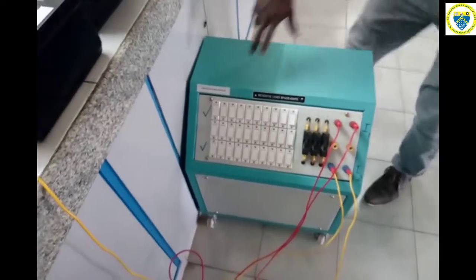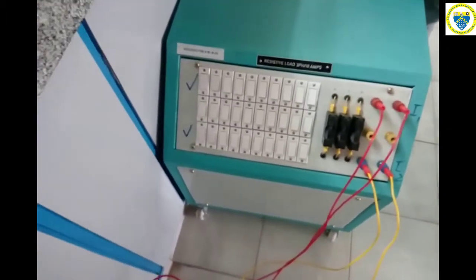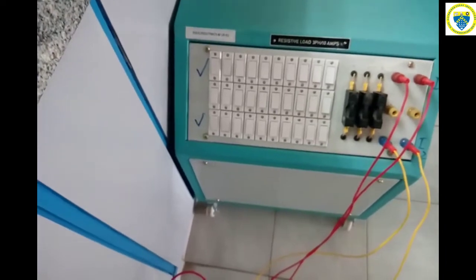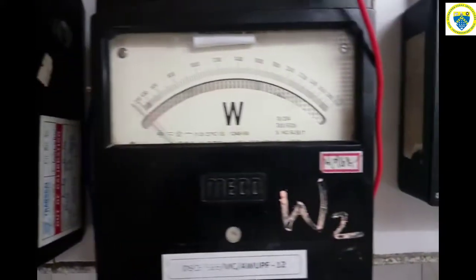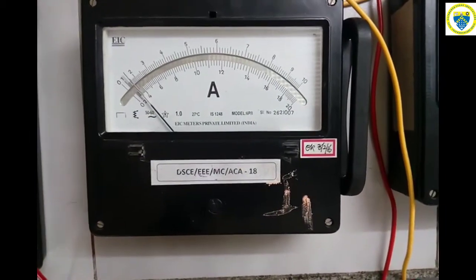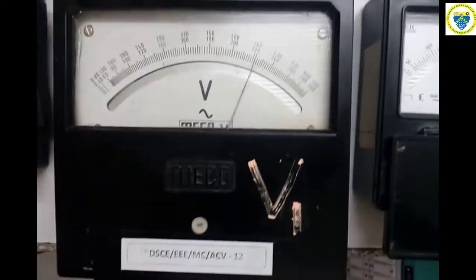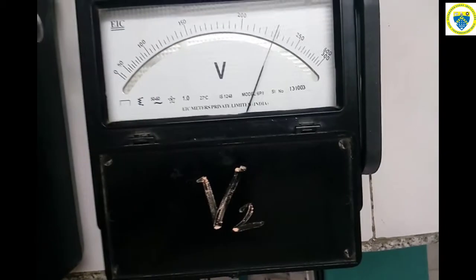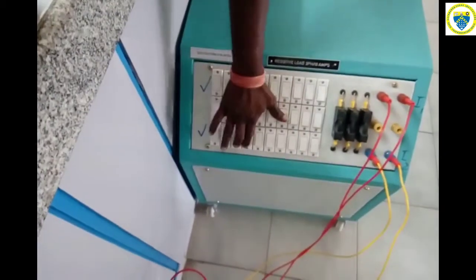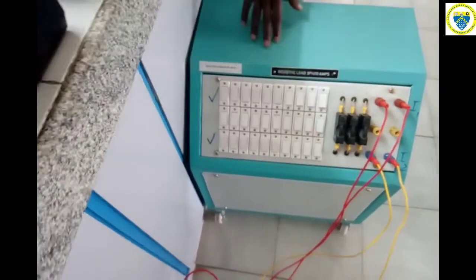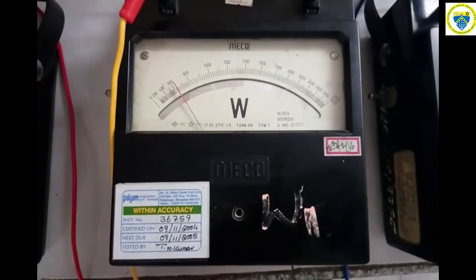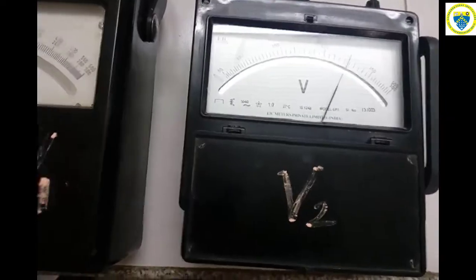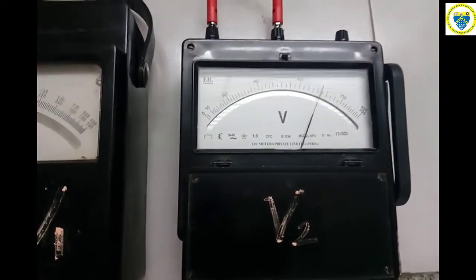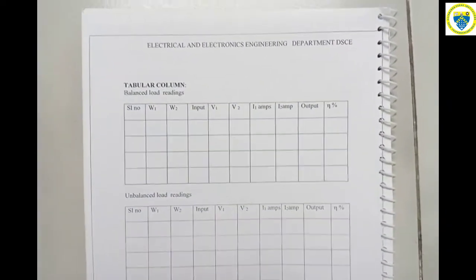First we have to apply the balanced load for transformer 1 and transformer 2, that means put on 2 switches for transformer 1 and 2 switches for transformer 2. Then note down the value of W1 and the reading of W2 and the current drawn from the transformers, I1 and I2. The corresponding V1 and V2 readings are also noted down. The loads are applied in steps to take the balanced load readings. So 2 loads each are applied and corresponding W1, W2, I1, I2 and V1, V2 readings are noted down. All the readings are tabulated in the tabular column provided in the manual. That is for balanced load.